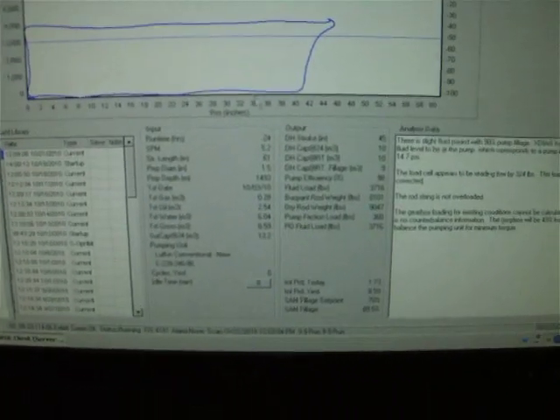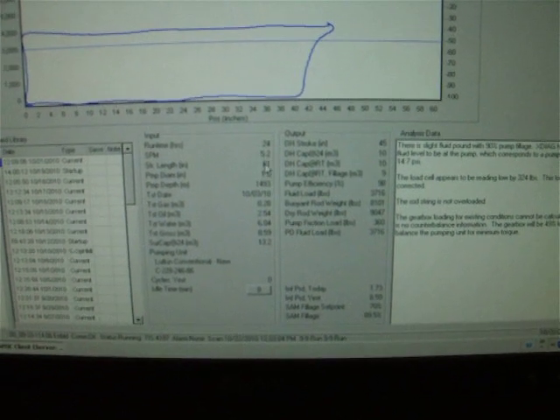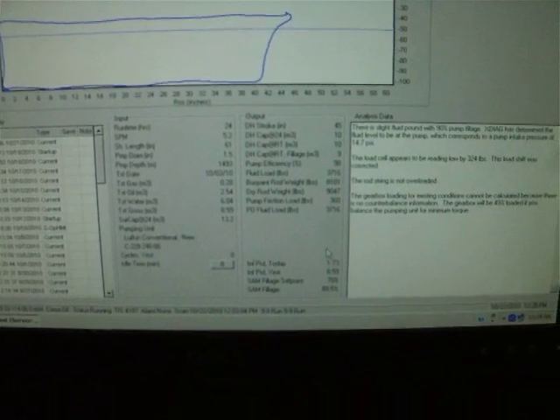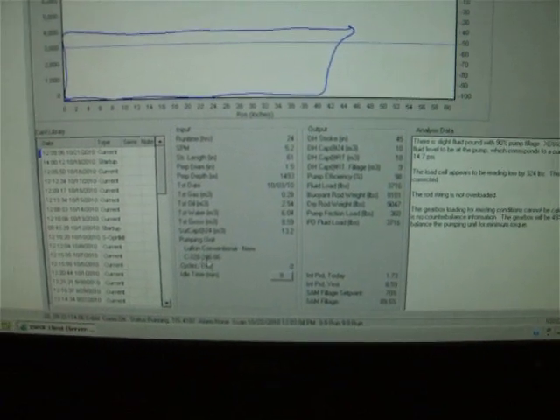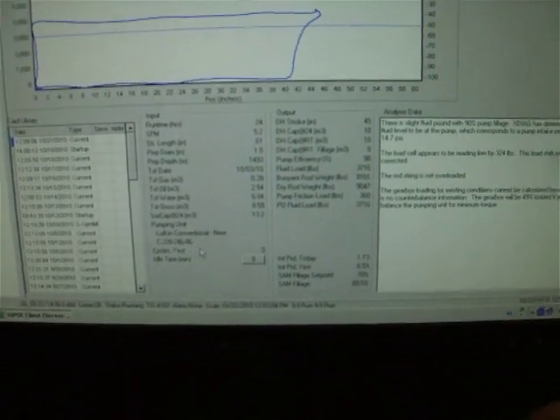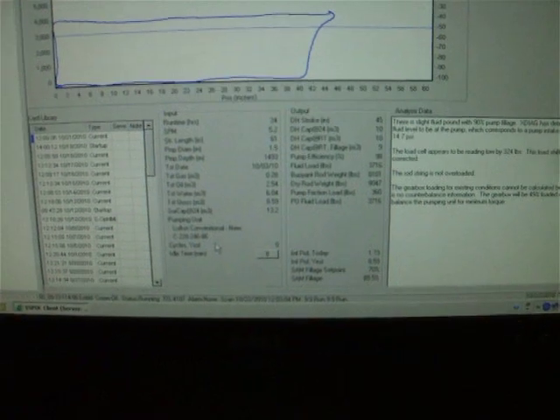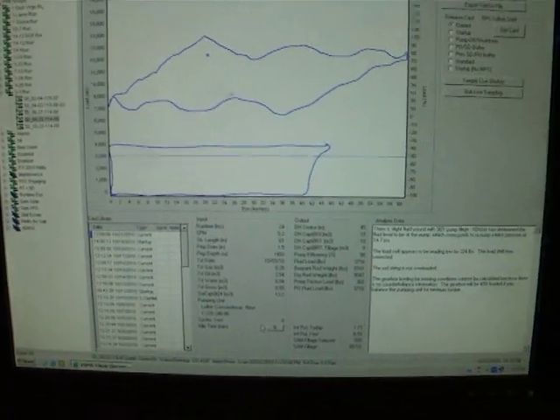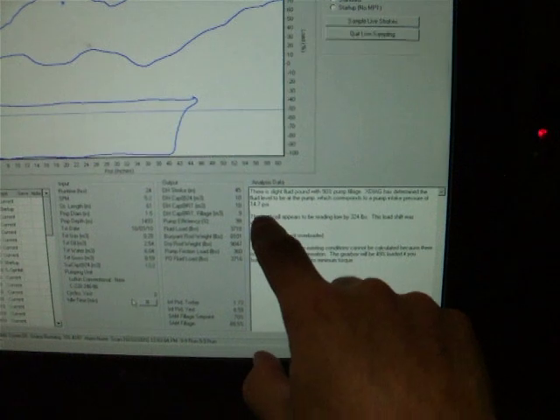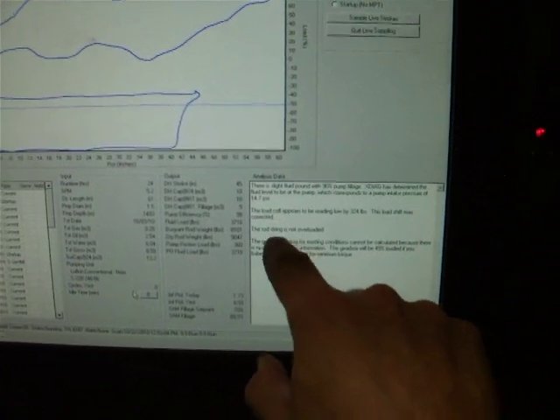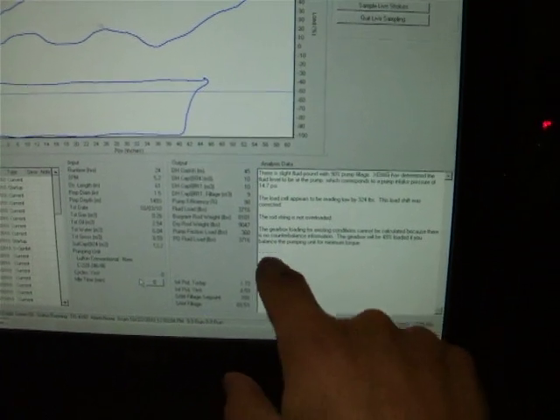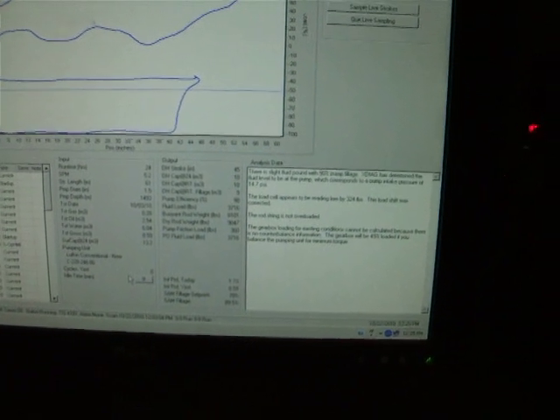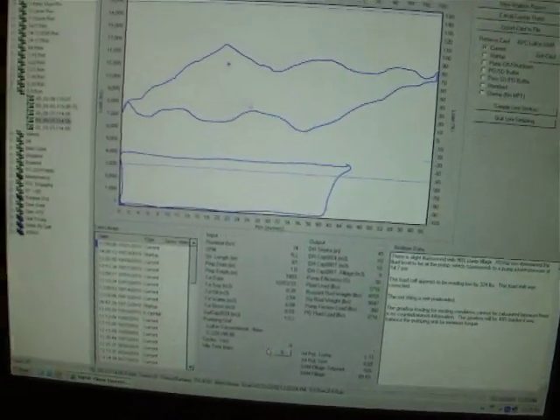Down here shows me 5.2 strokes a minute, 61 inch stroke length. It's a 226, 246, 86 pump jack. And we have 89% pump fillage. Over here's some information telling me the pump intake pressure. The rod string is not overloaded and the gearbox is 49% loaded. So we're in good shape here.